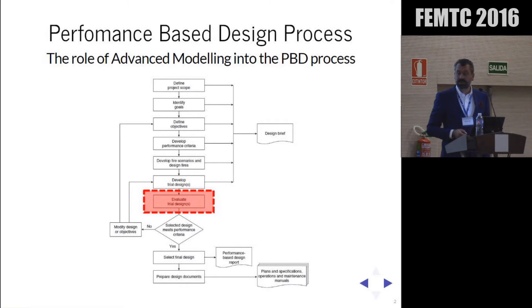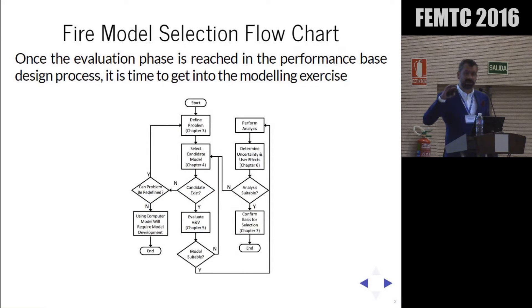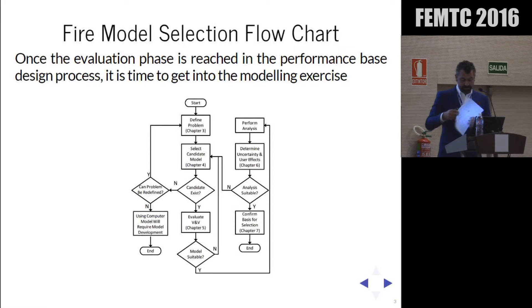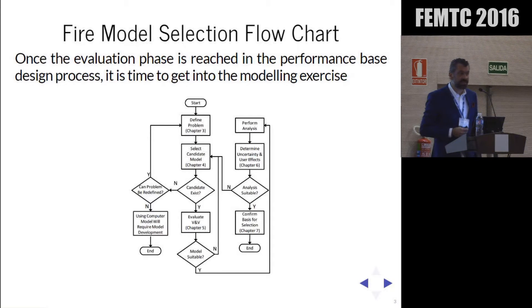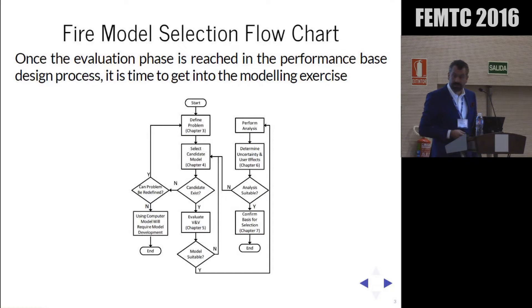You evaluate through your model — which can be algebraic, zone model, or CFD model — and you see if your design is okay or not, then come back to evaluate again. Once in the evaluation part, we need to select the right model, following the SFPE guidelines for substantiating a fire model for a given application. The process involves defining a problem, selecting a candidate model — whether evacuation, fire, radiation, flame spread, or whatever — and if it exists, proceeding to validation and verification before using that model.